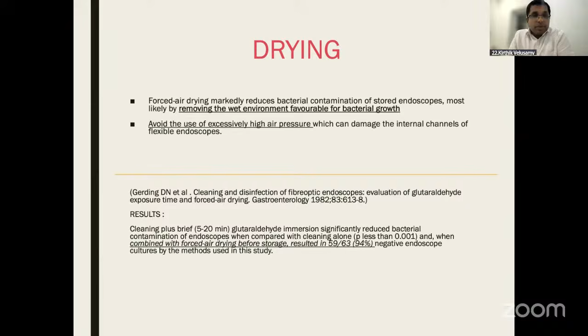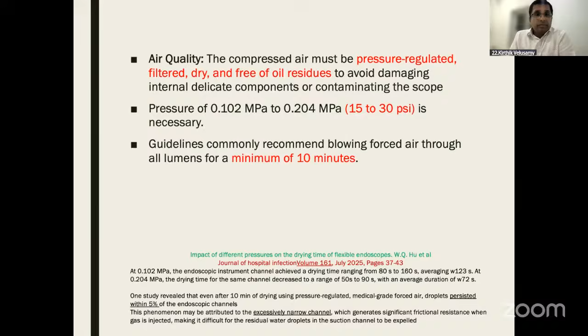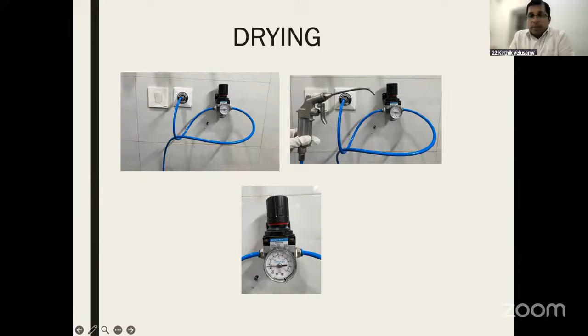Drying, we always use pressure regulated, filtered dry air, free of oil residues. Ideal pressure should be 15 to 30 psi, and guidelines recommend a minimum of 10 minutes of air drying. This is what I have in my hospital. This is a blue wire which is connected to the compressed air. This is the monitor which shows how much pressure we are using. This is the gun which we use to dry the instruments.